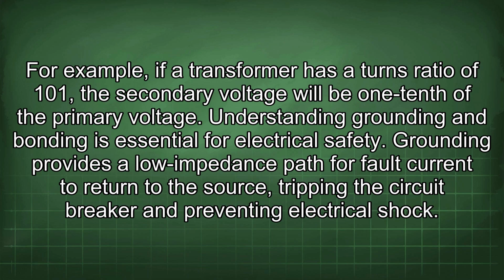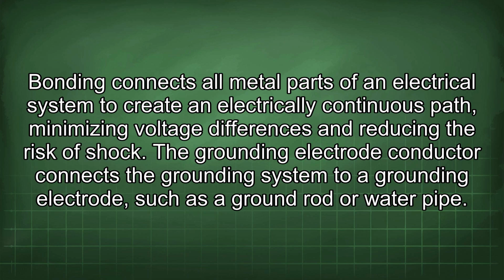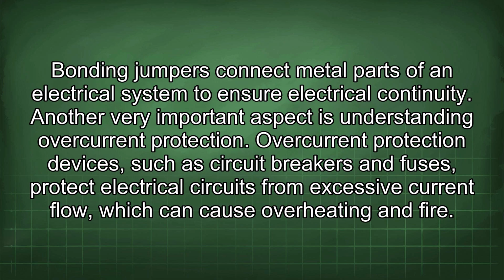Grounding provides a low impedance path for fault current to return to the source, tripping the circuit breaker and preventing electrical shock. Bonding connects all metal parts of an electrical system to create an electrically continuous path, minimizing voltage differences and reducing the risk of shock. The grounding electrode conductor connects the grounding system to a grounding electrode, such as a ground rod or water pipe. Bonding jumpers connect metal parts of an electrical system to ensure electrical continuity.